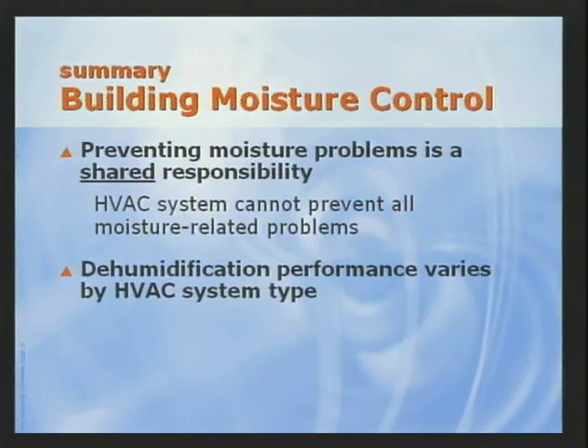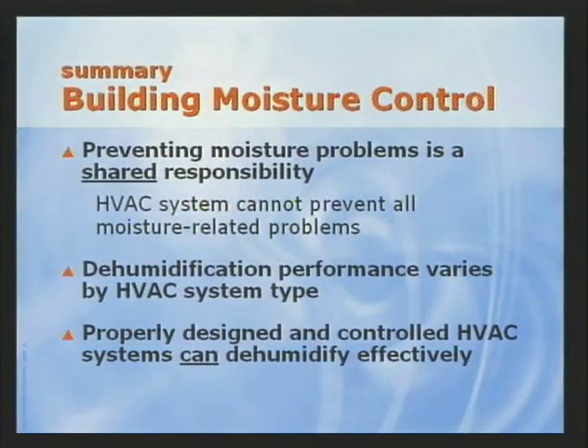Next, the dehumidification performance varies by type of HVAC system. The basic single-zone constant volume system is probably the most often used in schools. In some applications, in some climates, it may dehumidify just fine. In others, particularly for densely occupied spaces, and particularly in humid climates, enhancements may be required in order to dehumidify adequately at part load. Now, today we've shared several dehumidification enhancements for commonly used systems.